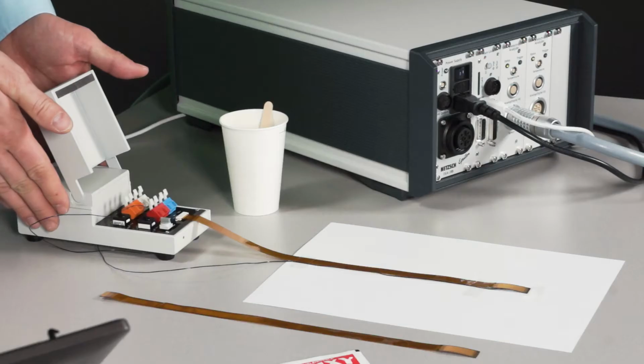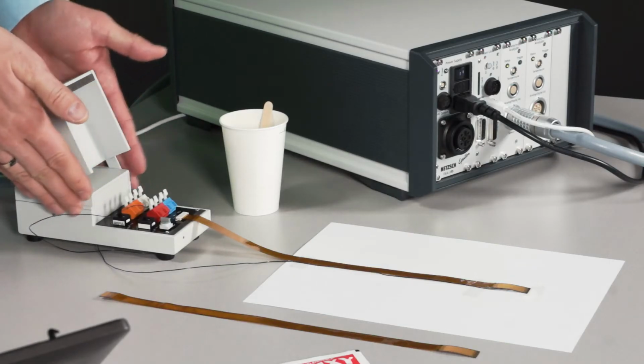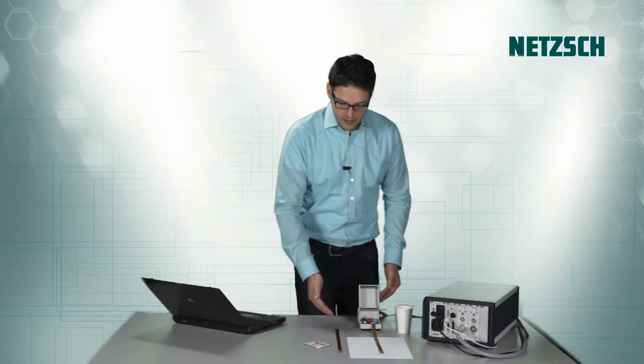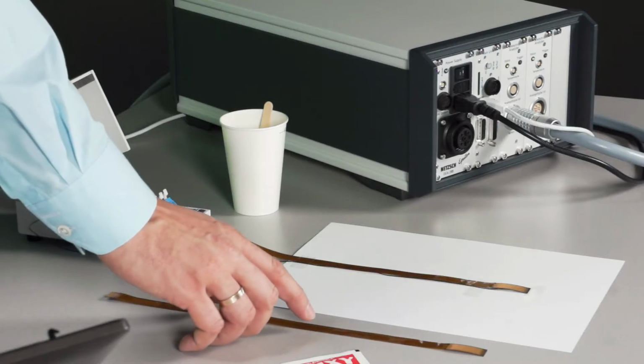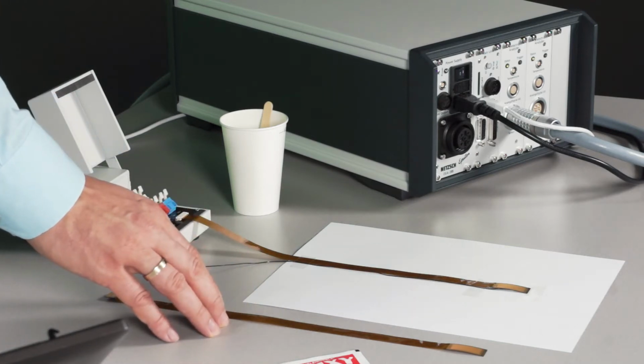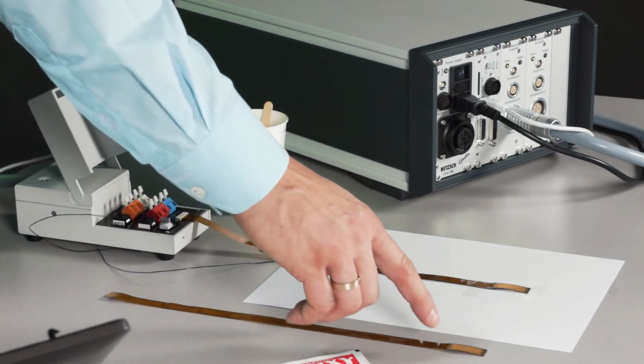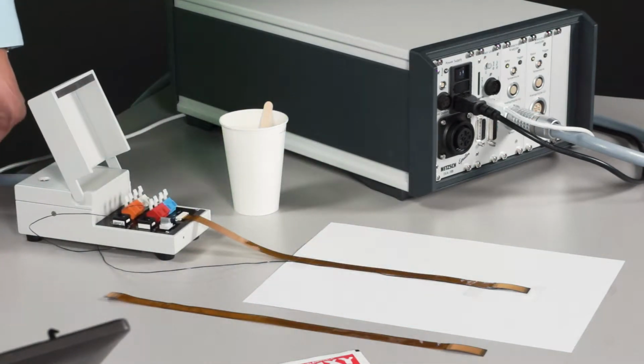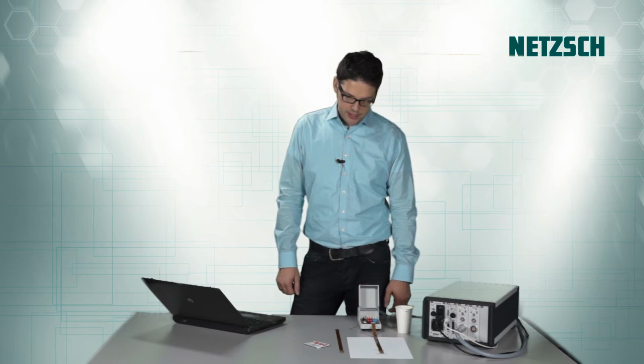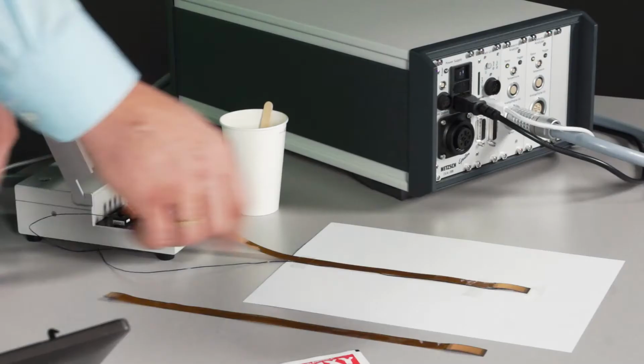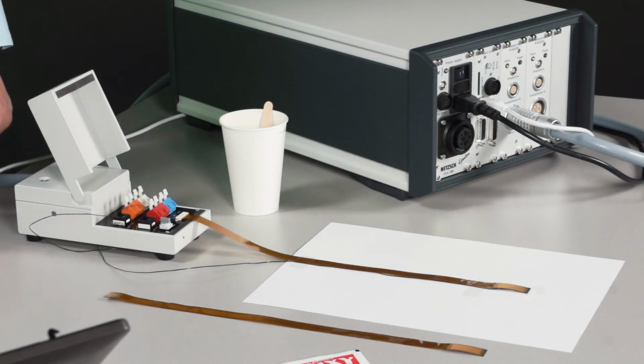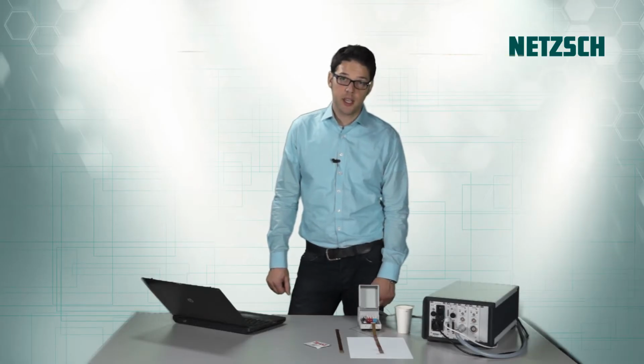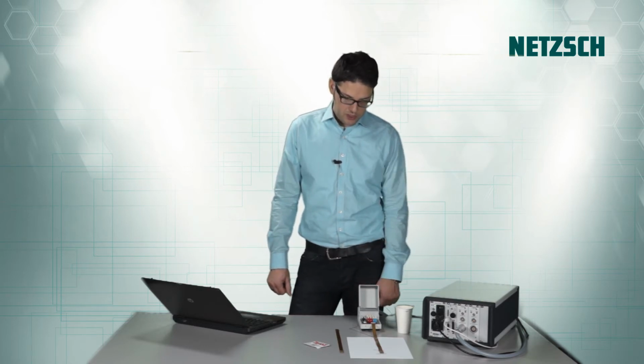To perform a measurement with a dielectric analyzer, you will need to connect a sensor to the instrument. Therefore, we have an adapter box which is capable of connecting sensors as well as thermocouples. Having a look at the sensor, it is a so-called IDEX sensor with a line spacing of 115 micrometers. This means that the lines between the anode and the cathode have a distance of 115 micrometers. In total, the sensor has a length of 35 millimeters. For special applications, there are extension cables available, but in this case, we have not used any.